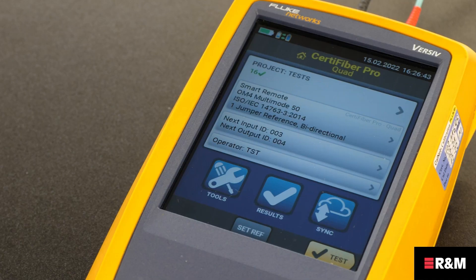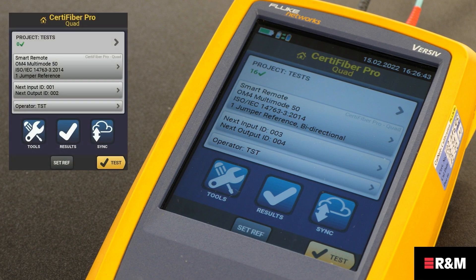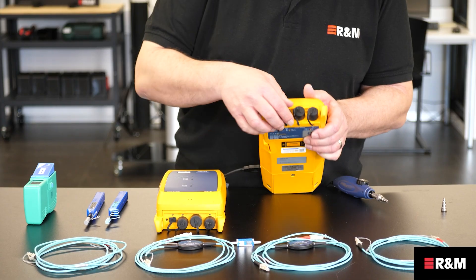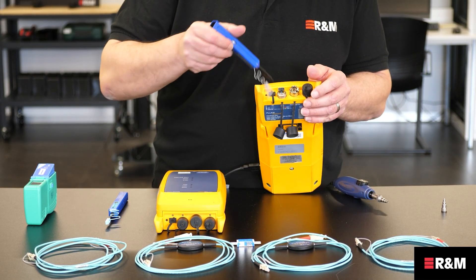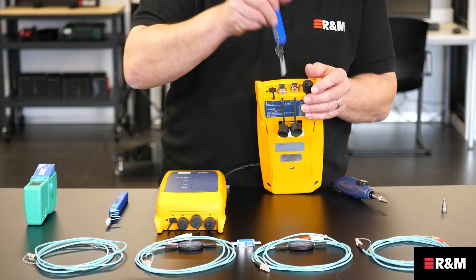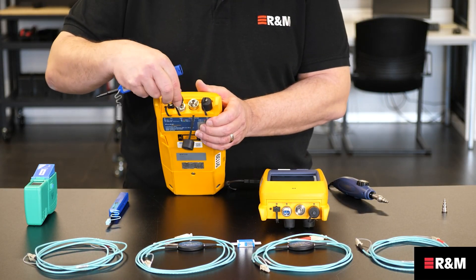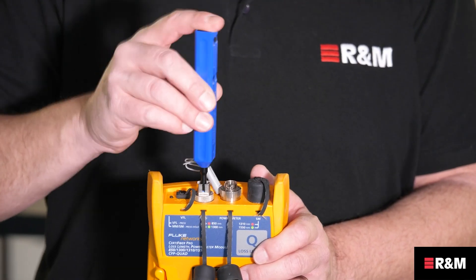Now let's begin to set the reference. Turn on the tester and remote and let them sit for a minimum of 5 minutes or at least for as long as they need to attain the ambient temperature. Make sure that the home screen shows the correct settings for the job and the test type is Smart Remote. First, please clean the connectors on the main tester and don't forget to do the same for the remote end.